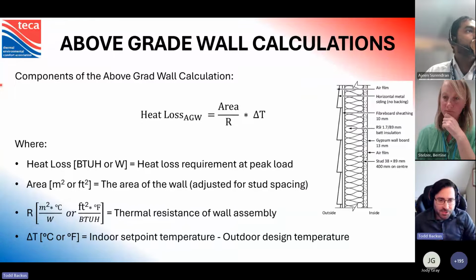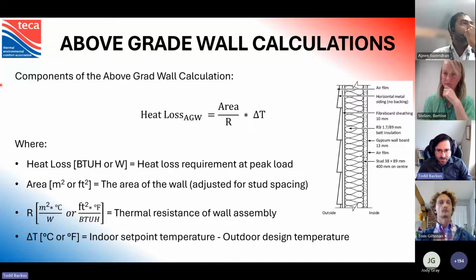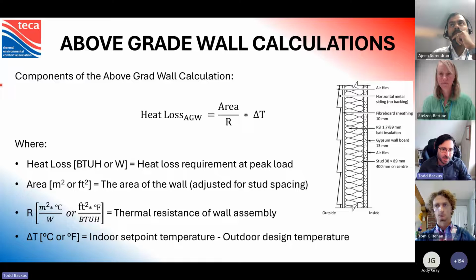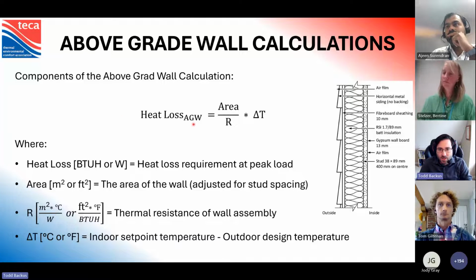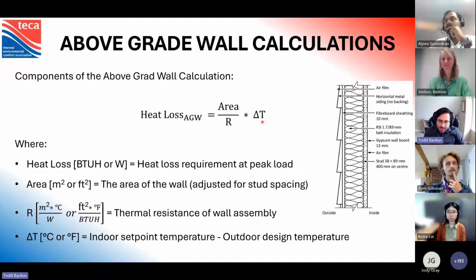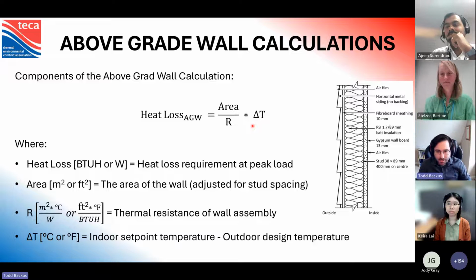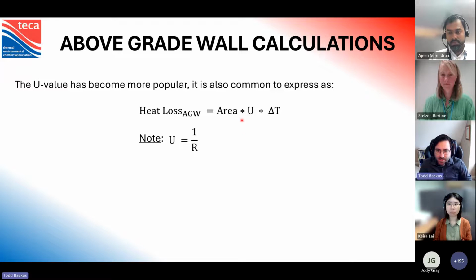I'm not going to go really far into the math behind the calculators because it's just much too much to cover in such a short time, but I do want to highlight a couple things about some of the calculations. So here we're looking at the heat loss of an above grade wall assembly. This kind of calculation shows up a lot in the CSA F280 standard, where you'll have the area divided by the R value times the delta T. And that delta T is the difference between your indoor set point temperature, so the temperature that you want inside your home, minus the outdoor design temperature. And you see this calculation come up many, many times in the back end of these calculators. You will also see it's quite common to replace the R value with U, and that way it just keeps it straight multiplication, but just note that the U value is just 1 over R, so it's essentially the same thing.